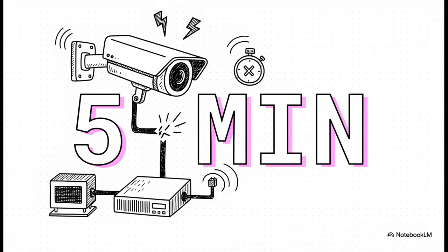Why is that little gap so important? A 30-second delay, what's the big deal? Well, here's the big deal: if a modern IP camera loses power for even a split second, it has to completely reboot, and that boot-up process can take up to 5 minutes. So without a UPS, that 30-second generator startup time means your entire facility is completely blind for 5 full minutes.